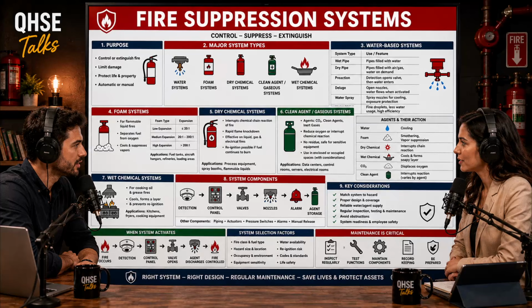Its primary mechanism is physical smothering and vapor sealing. When you apply foam to a massive burning liquid fuel spill, it flows across the surface of the fuel. It physically separates the flames from the fuel source. But more importantly, it forms a microscopic aqueous film over the fuel. This film completely suppresses the release of flammable vapors. If there are no vapors rising, there is absolutely nothing for the fire to burn.